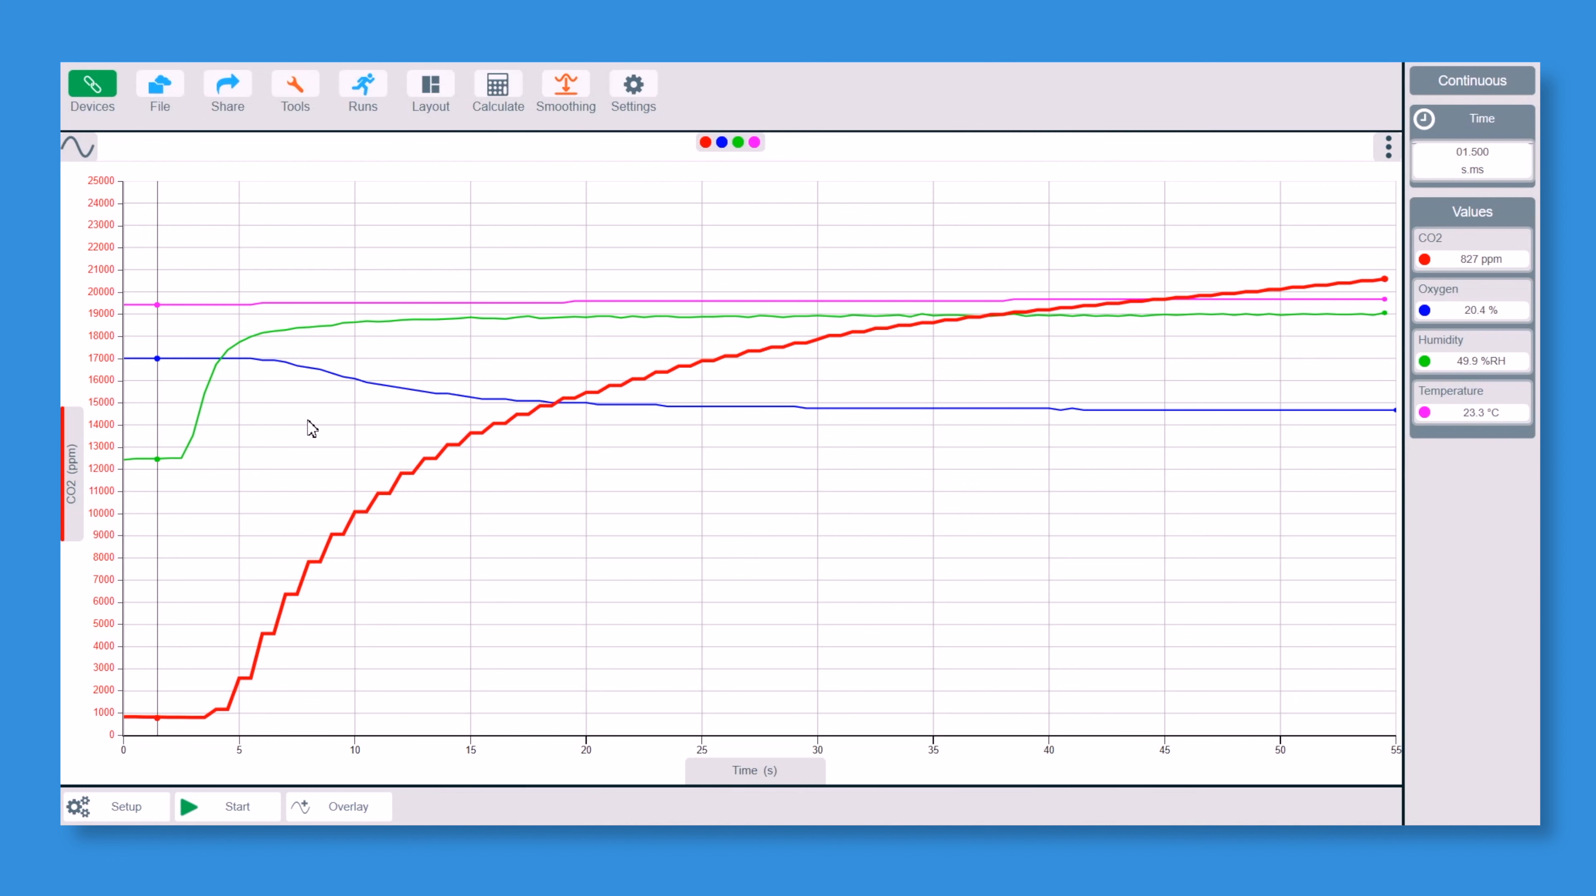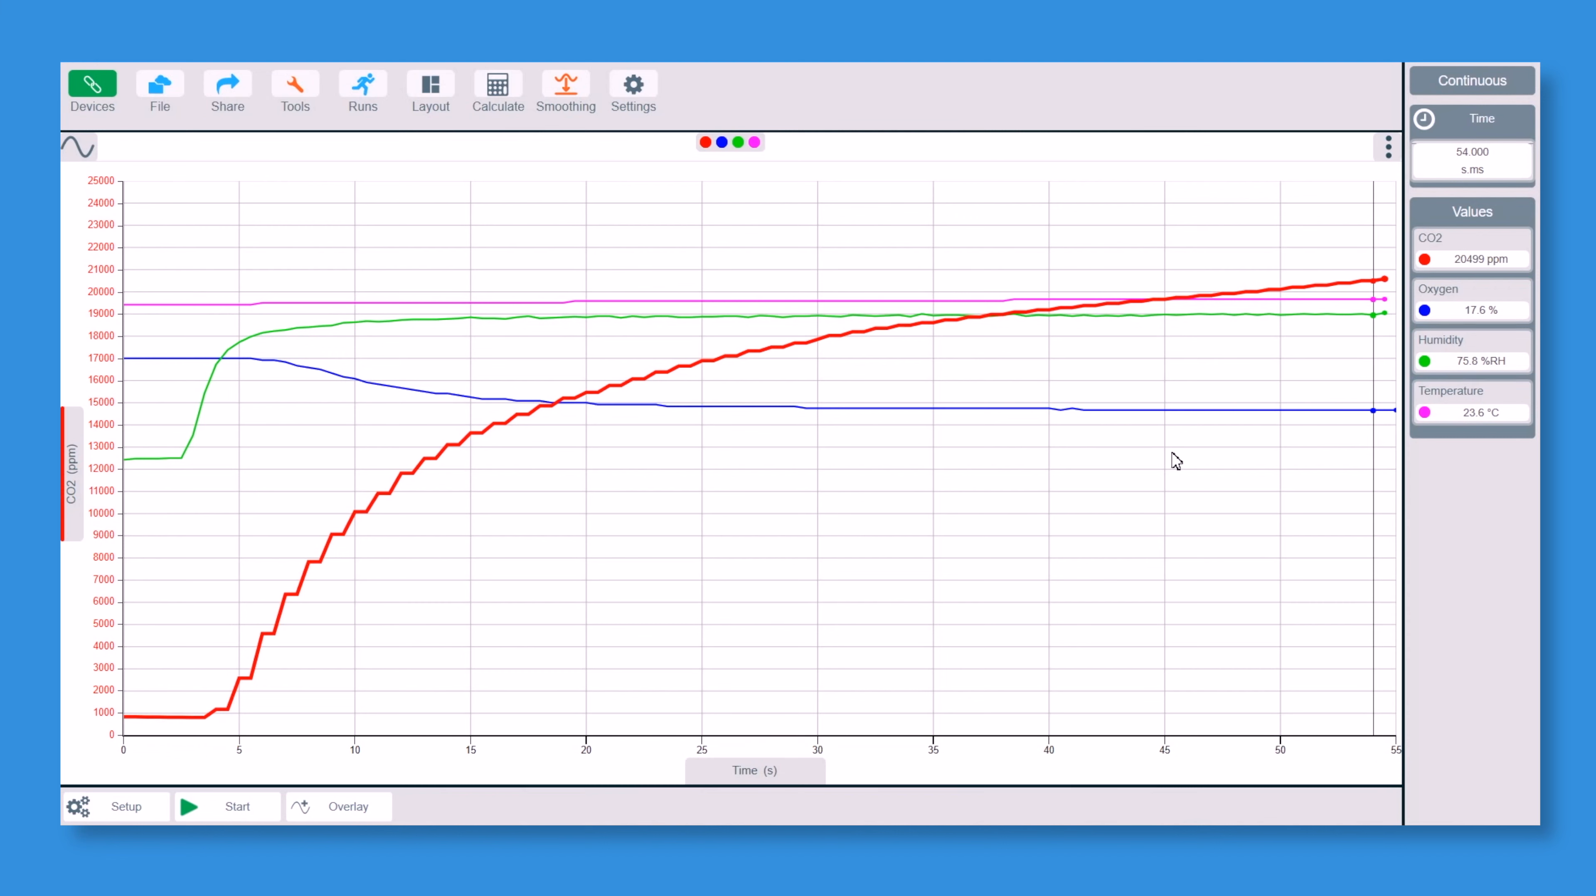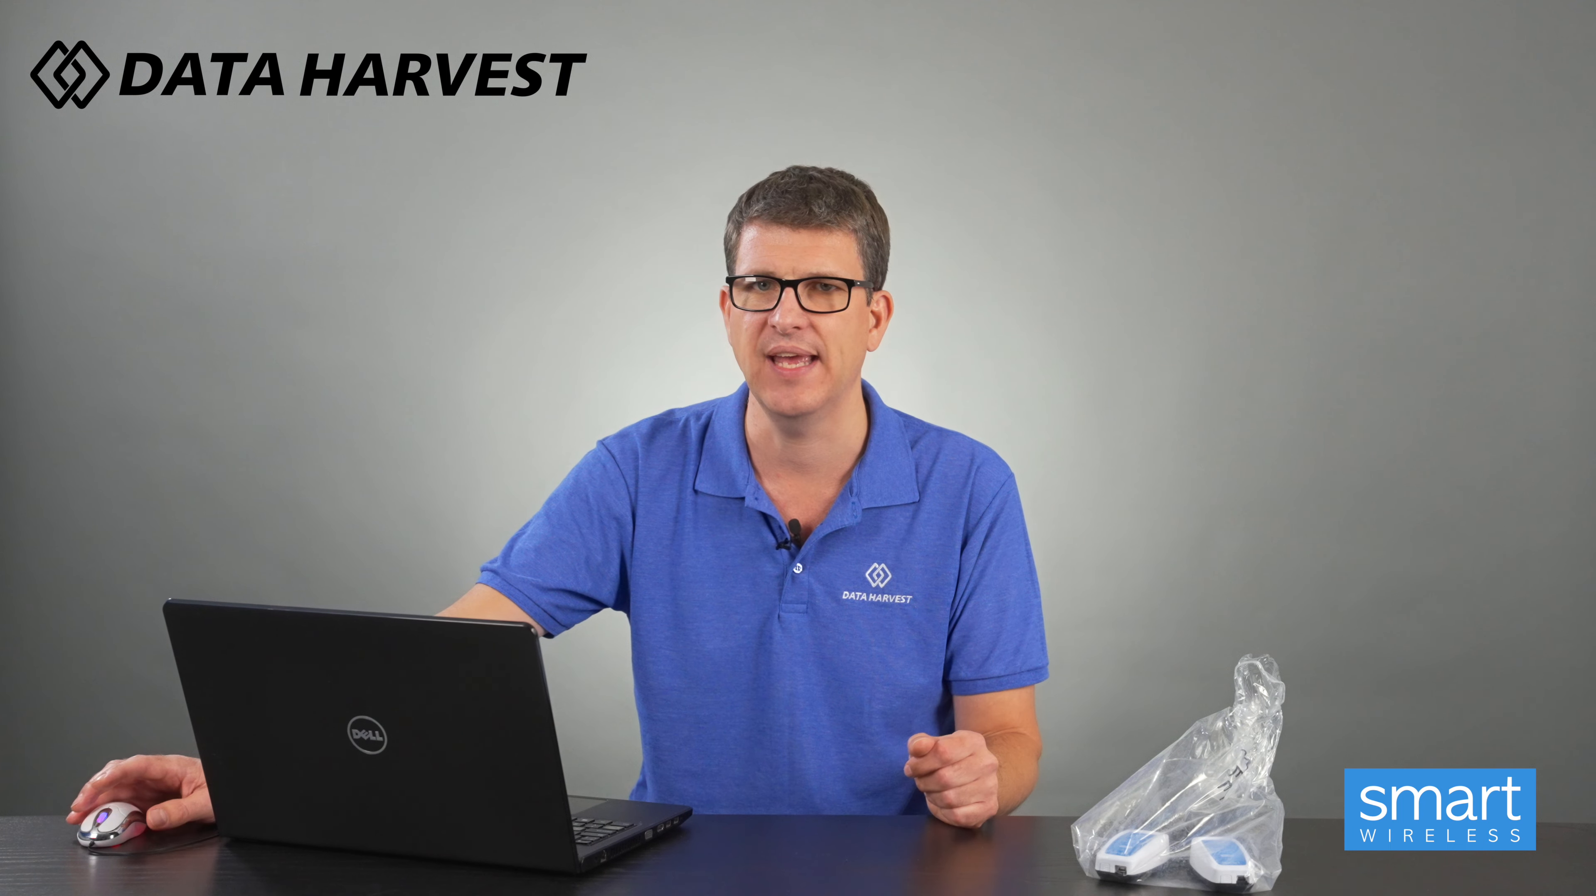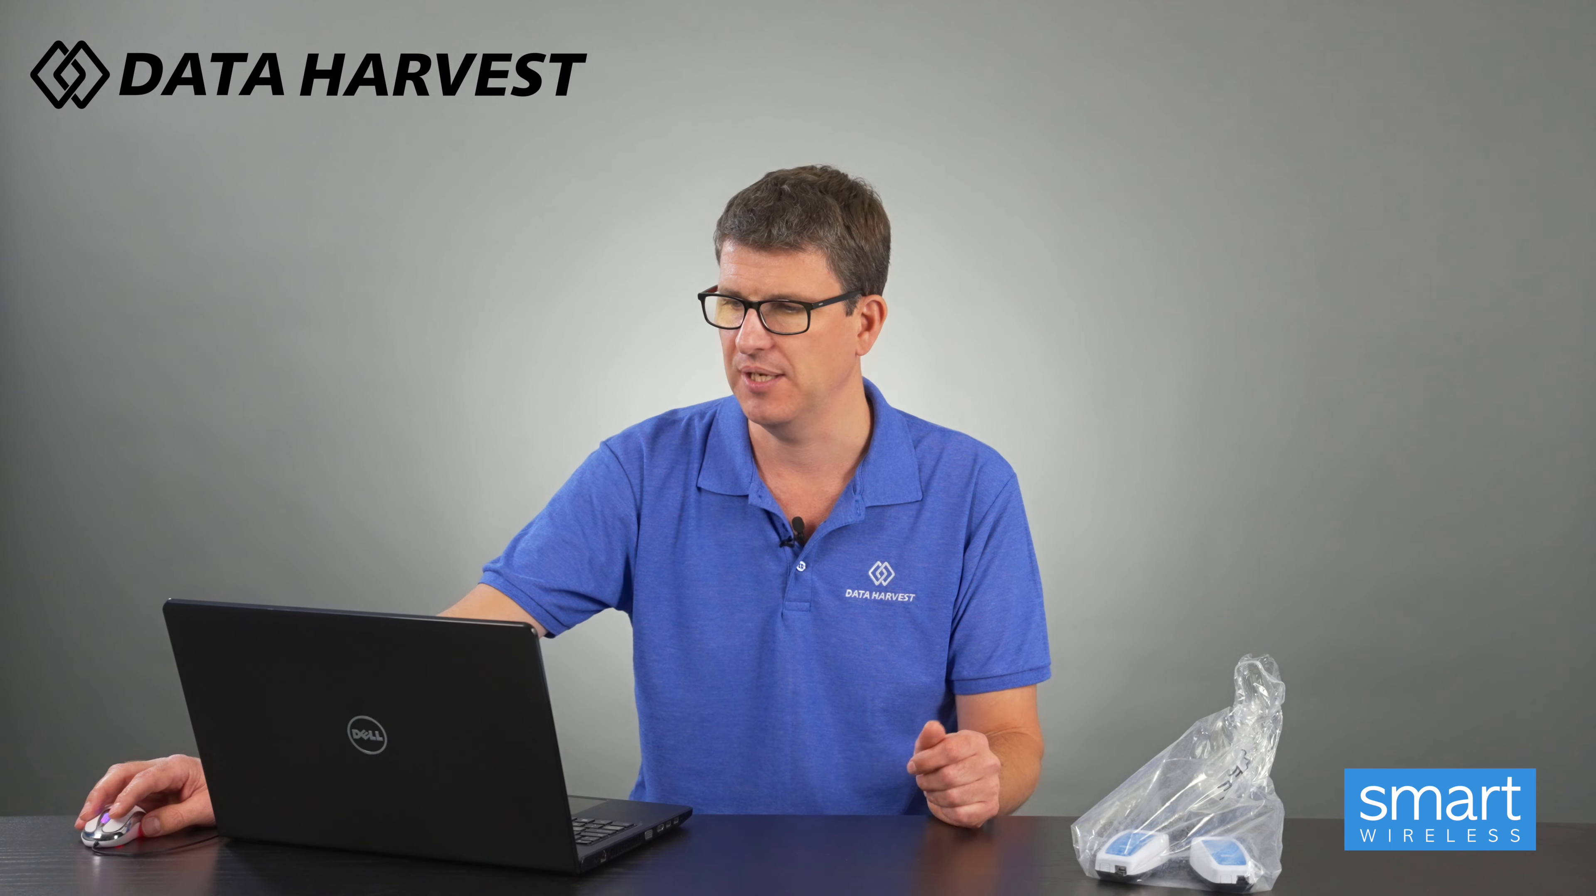But at its peak, well towards the end, if we go right over to here, you can see CO2 has gone up by 20 fold, oxygen's dropped down to 17.6, humidity has gone up a lot from 46 to 75, temperature's stayed pretty level, which you expect maybe 0.3, 0.4, 0.6 maximum change there for the temperature.